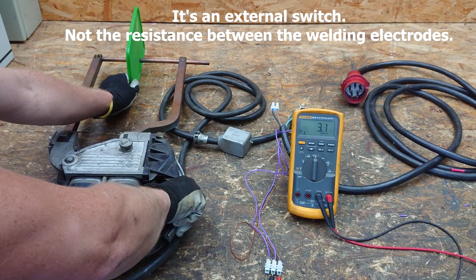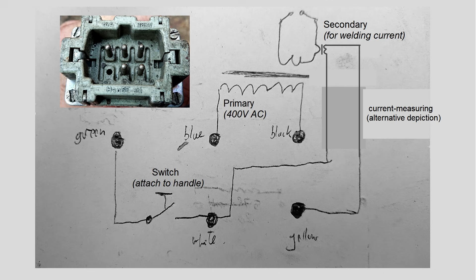Another wire seems to lead to another winding on the transformer core. I deduce that by measuring the inductance between the contacts here. While the main secondary winding connects to the massive copper bars, allowing for a low voltage, ultra high current output, the purpose of that third winding might be to measure the secondary current, providing a feedback signal to the circuit that controls the spot welder.